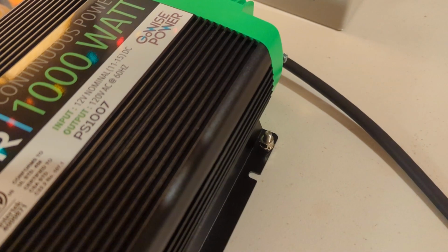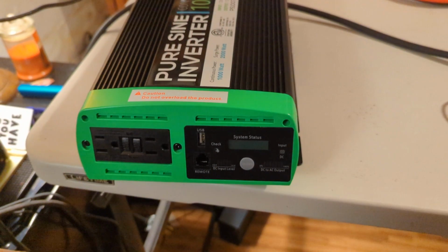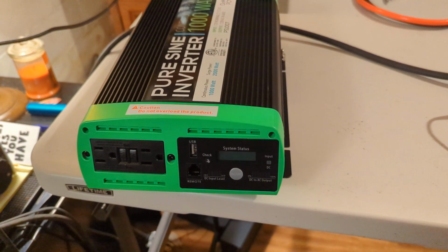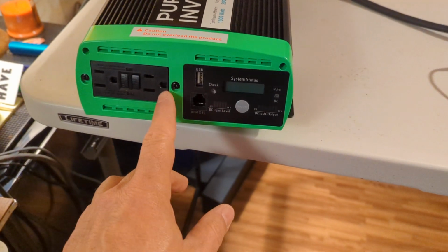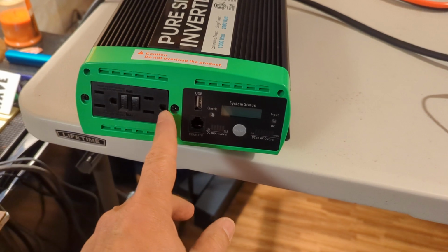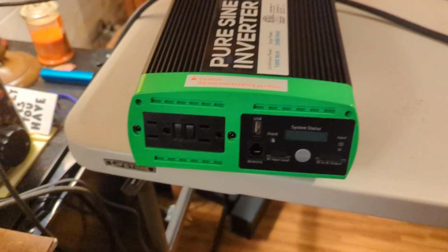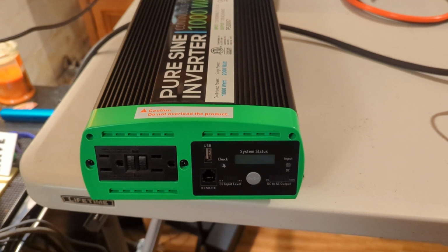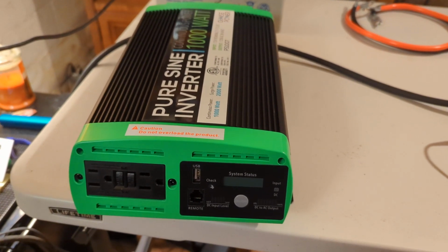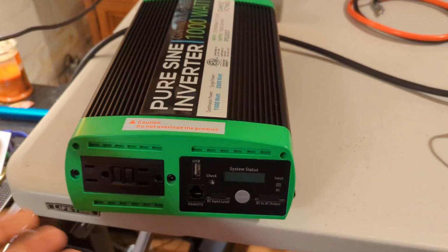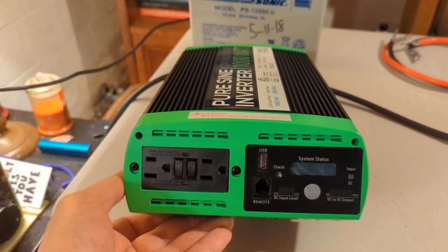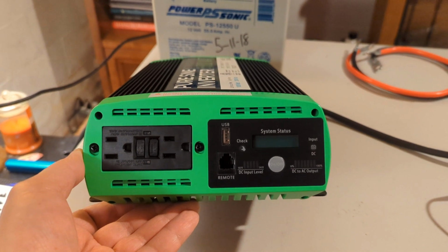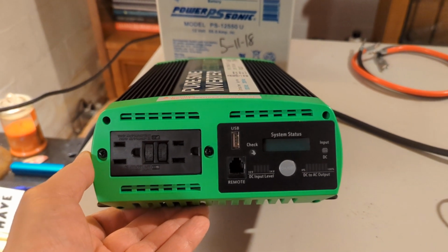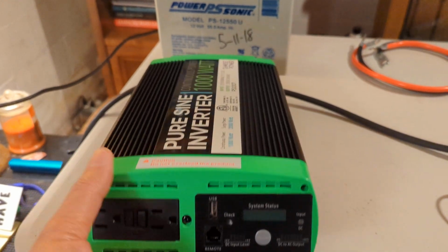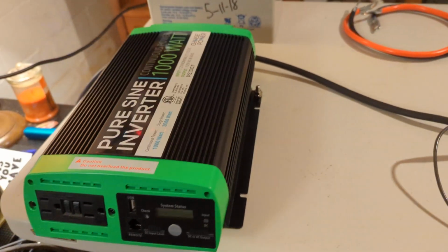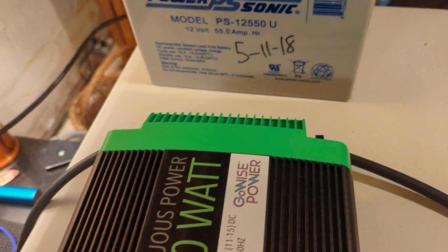One measurement we're going to check when running this is whether the ground lug is actually connected, and whether this has a floating neutral or if the neutral and ground are bonded together. That's unknown — no one was able to answer that question in the Amazon listing's product questions section. So we'll see. This comes without any cables whatsoever.